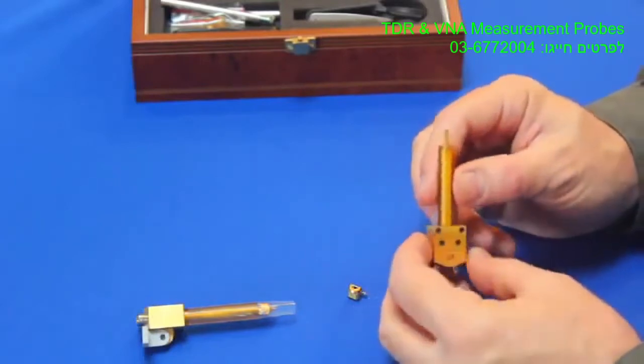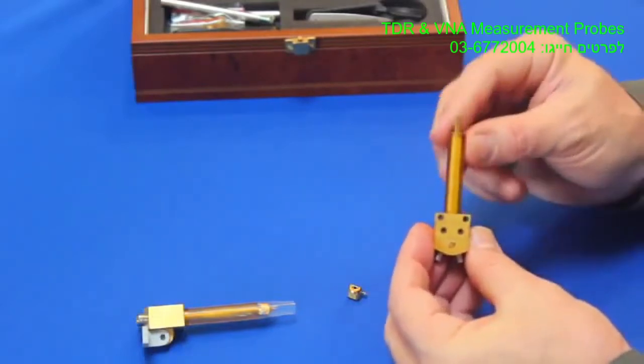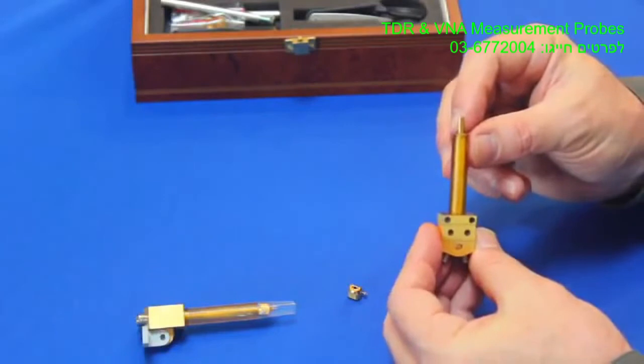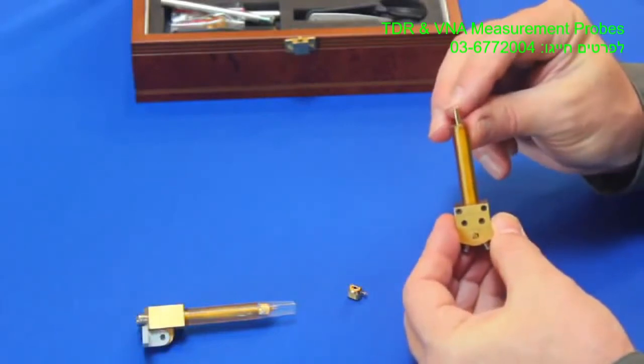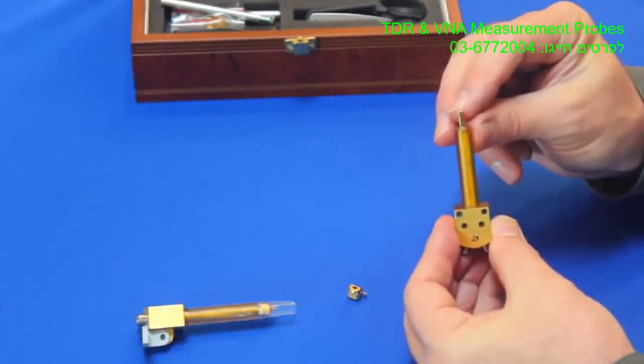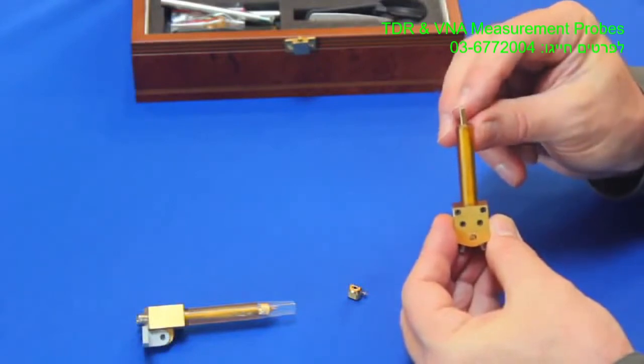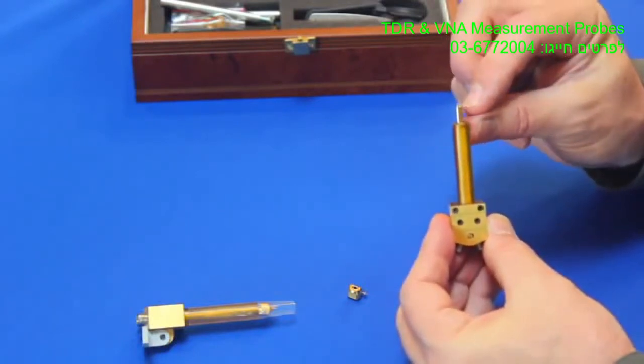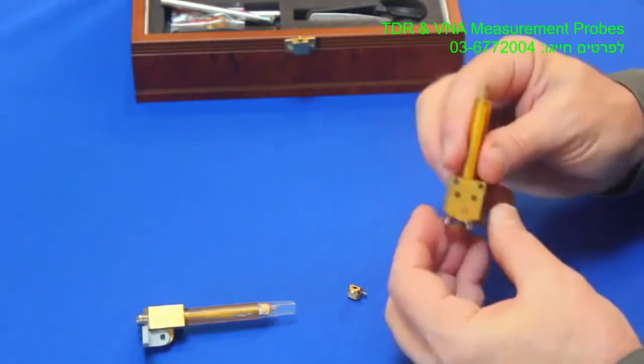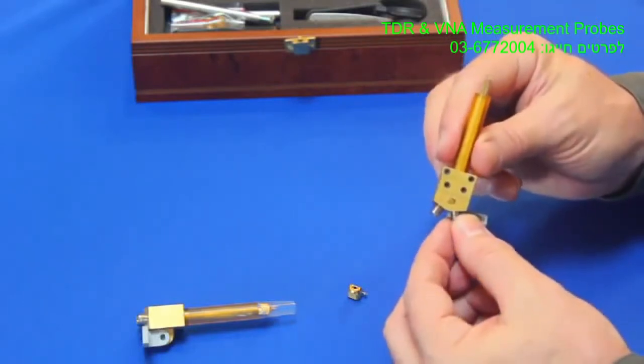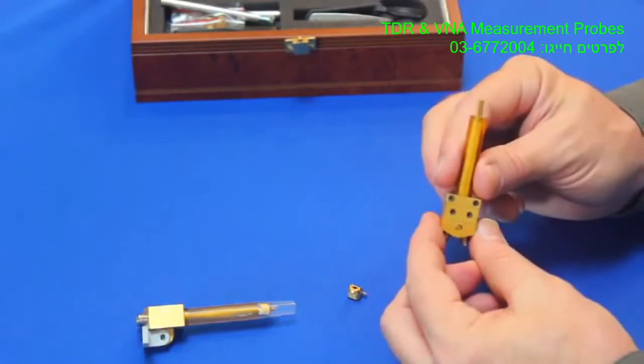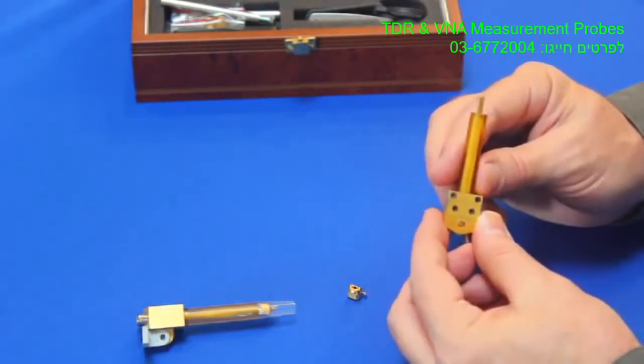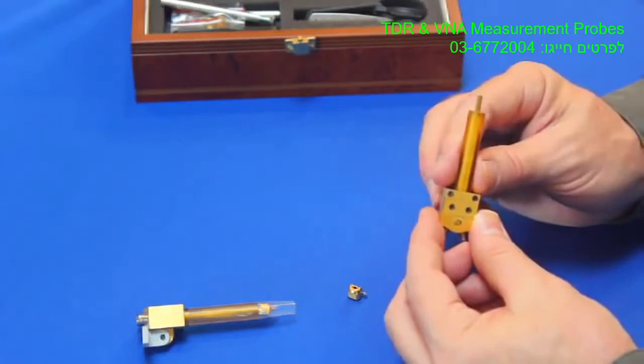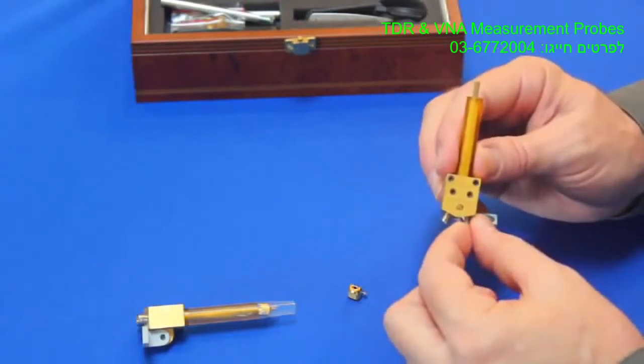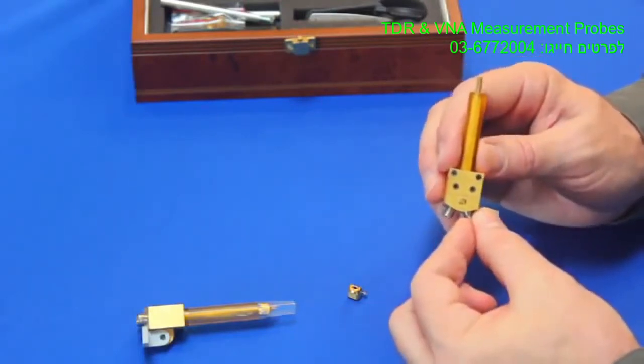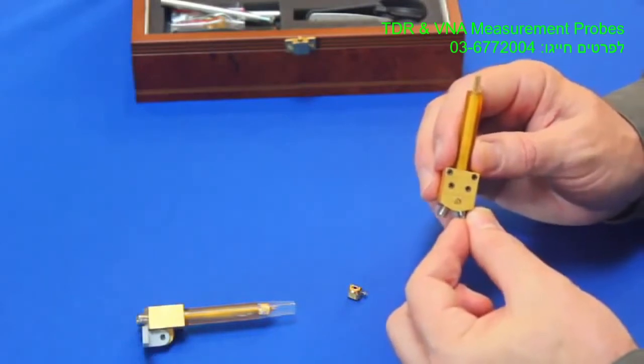In the most basic mode, without the ground collar, the probe has 100 ohm between these 2 signal pins that you see here. And if I short one of the pins to the outer shield and put a ground cap on it, then you have a 50 ohm probe. The probe has approximately 4.5 picosecond loss in the probe itself, and a 40 gigahertz bandwidth. That includes your insertion and return loss.